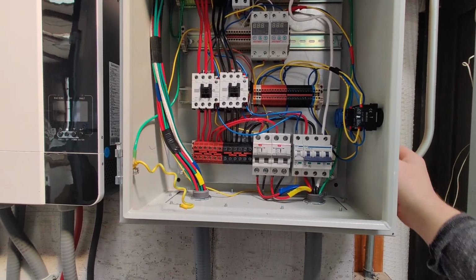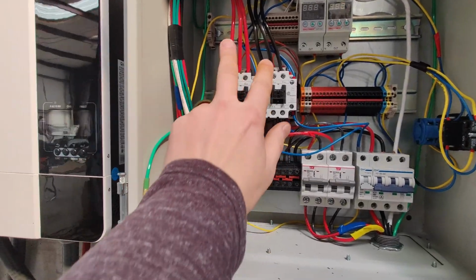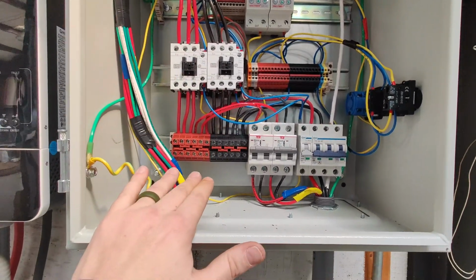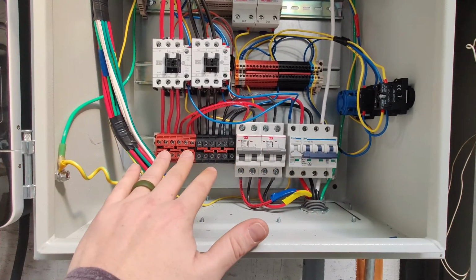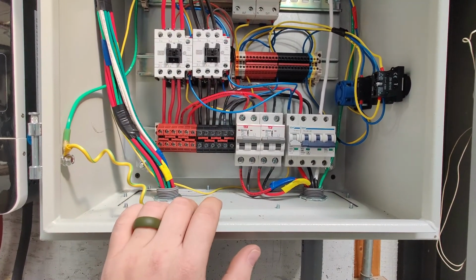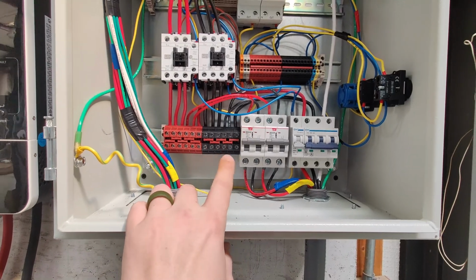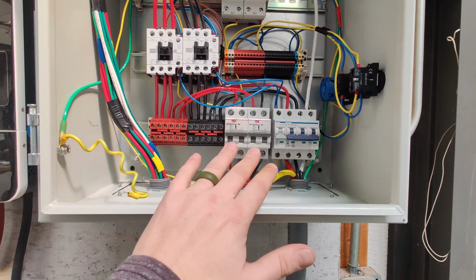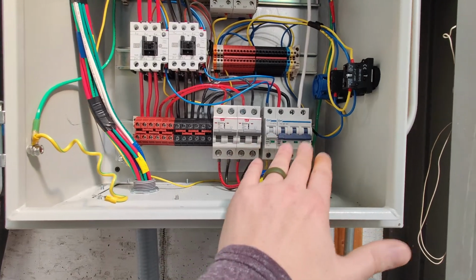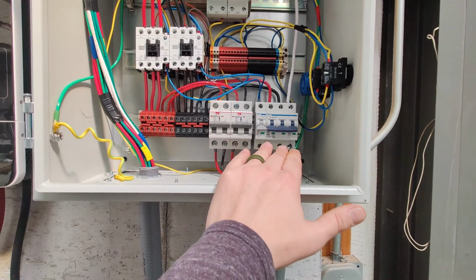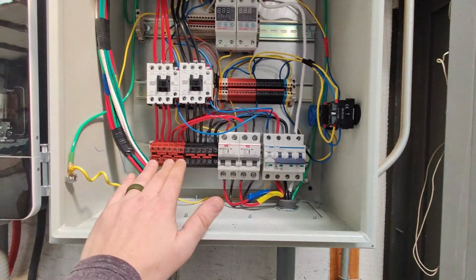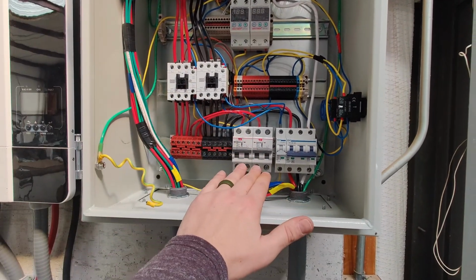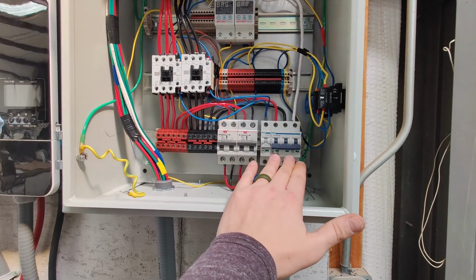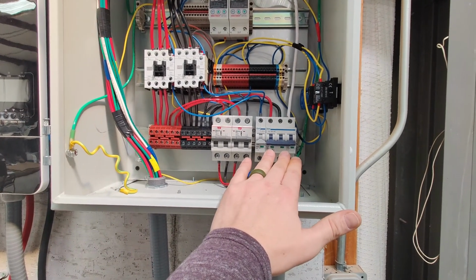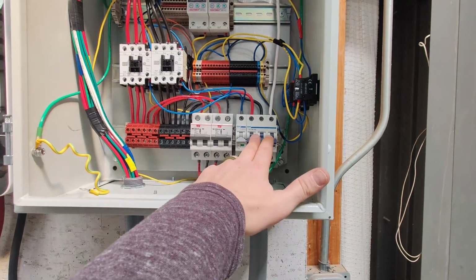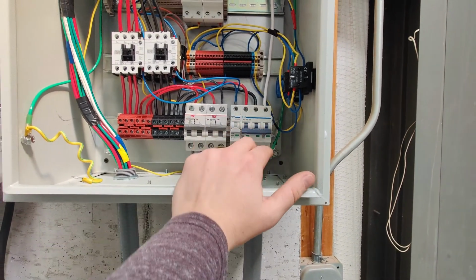When I turn this off, not only did my contactors disengage, but when the contactors disengage, that kills the hot for the whole system. As soon as these contactors open, the hot legs no longer allow electricity to go to the auto transformers or out to your loads. So it's a hot kill for the circuit that feeds the auto transformer and the circuit that feeds your actual loads, which is what you're looking for it to do.